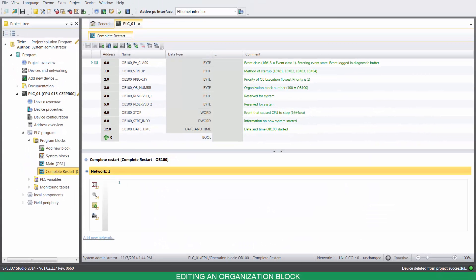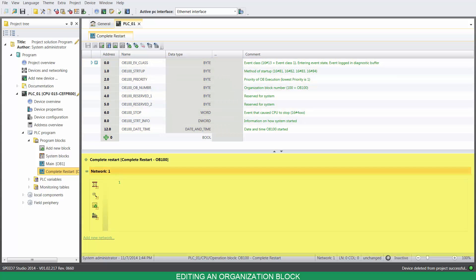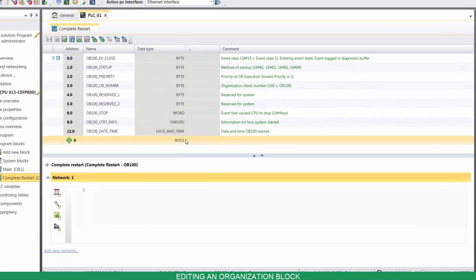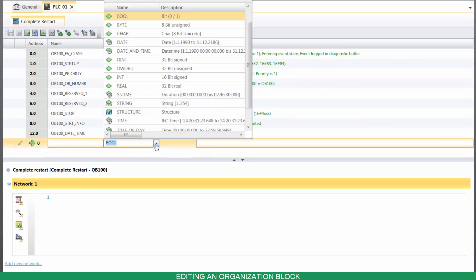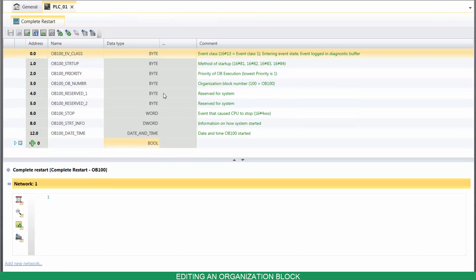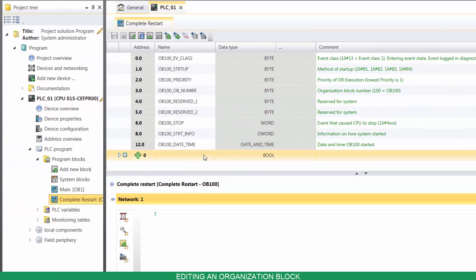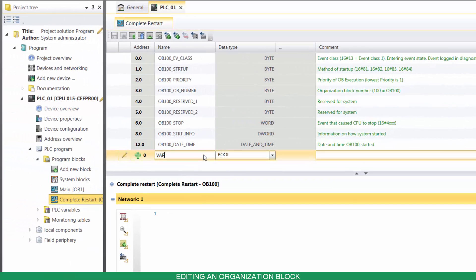The OB editor has two sections. The Declaration section, where you can define all the variables used in the block. And the Program section, where you enter the instructions to be executed by the control. To add a new variable, select its data type, name it, and then press Enter.